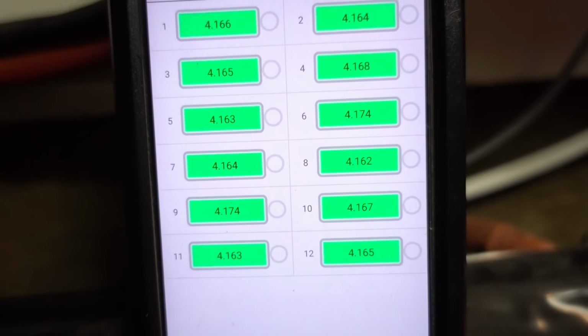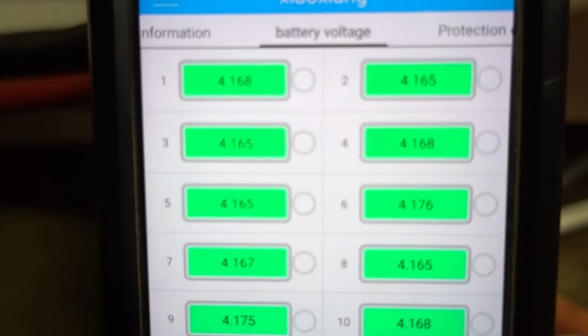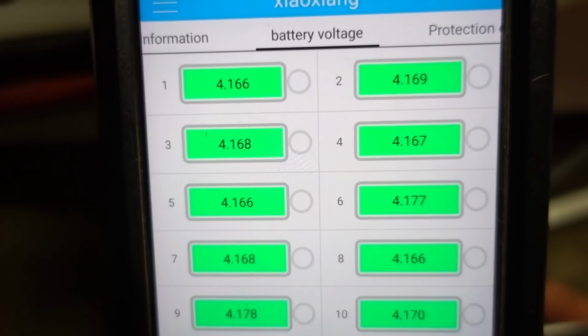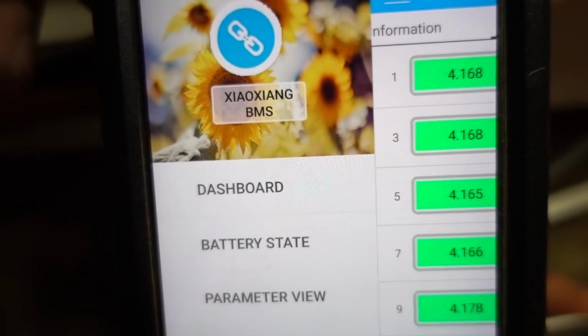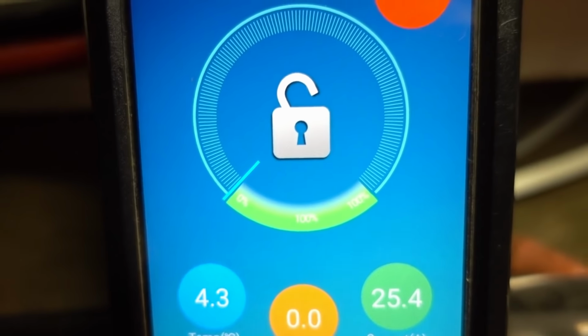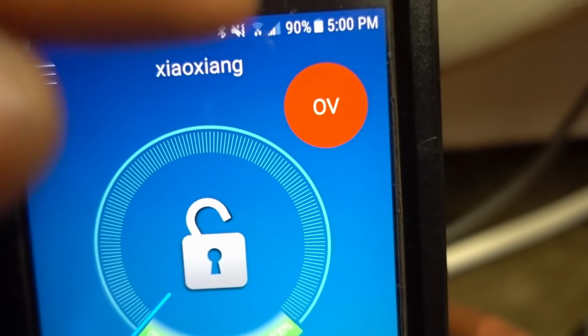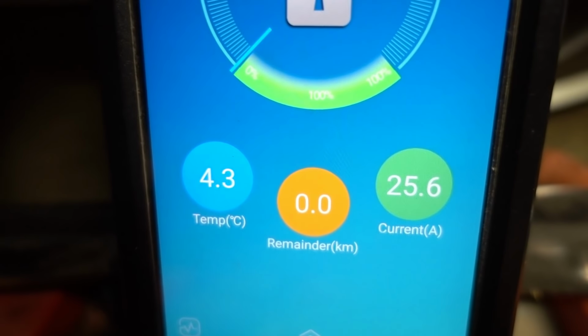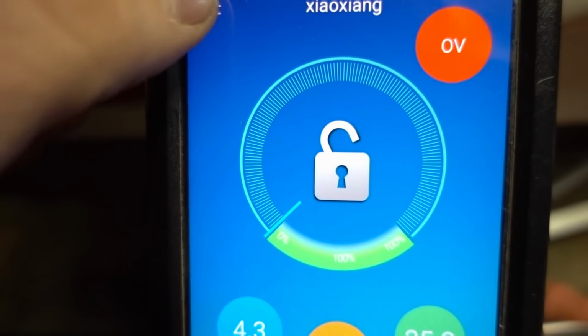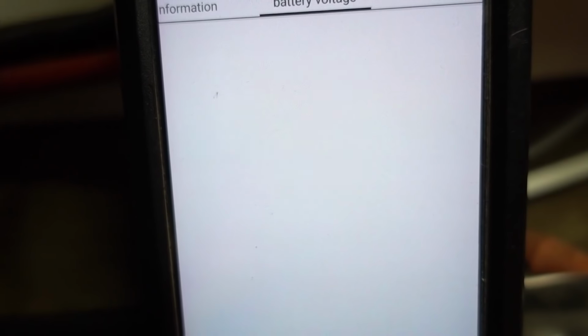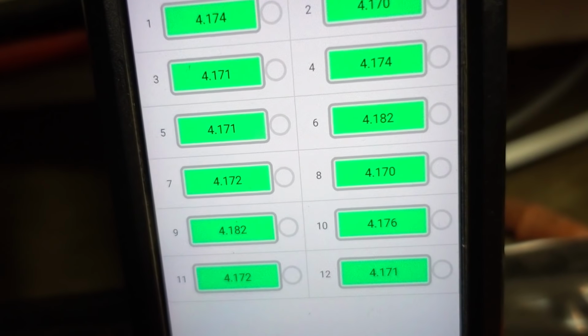I have this set to 4.1 volts per cell, and obviously that's over that. So if we check the dashboard, what's it say? Oh no, overvolt - it's at 100% and we're still charging it. It's saying bad, so what does that mean? It means it does not cut off on the pull side.